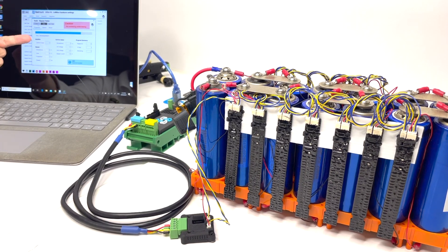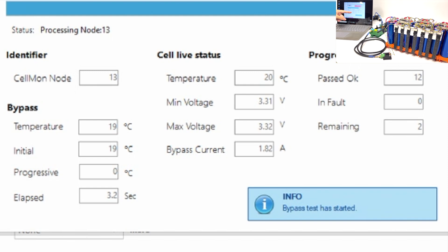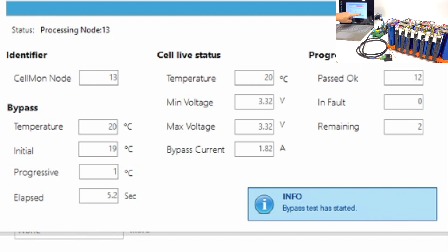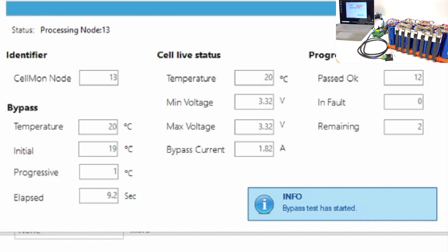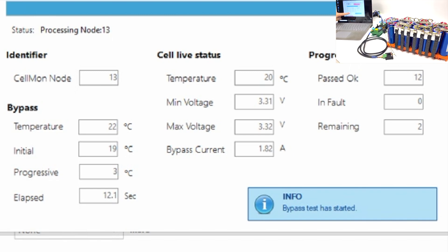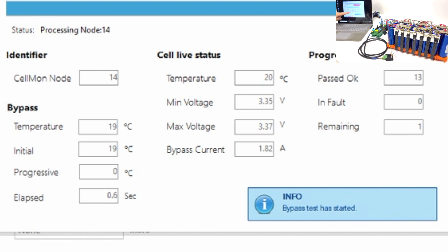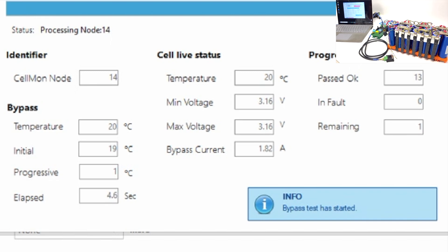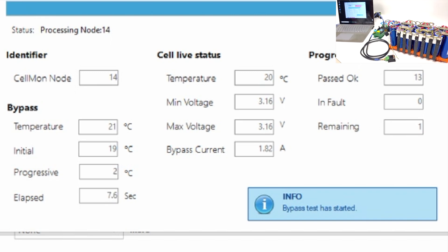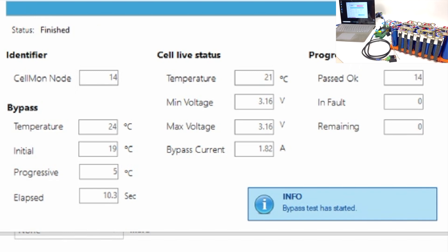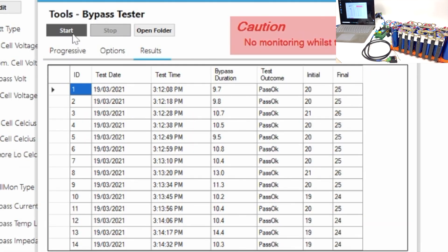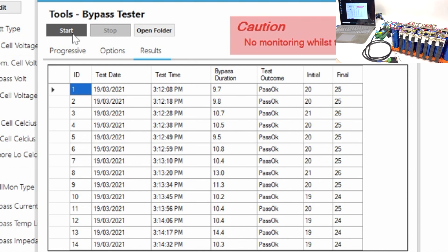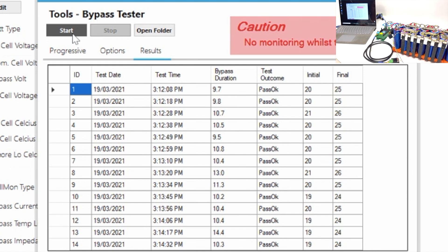Okay so now we're on to cell 13 of our 14 cells. 12 of them have passed with the last two that it's testing now. So it's just making sure over a period of time we're up at 10 seconds now that it's increasing in temperature up to four degrees, finally the fifth degree and we're now testing our last cell. So it started at 19 degrees and it's going to work itself up to 24 degrees. Once we're there we're going to be quite happy that we can confirm the device is done. It now shows it's finished and it gives us a test report.